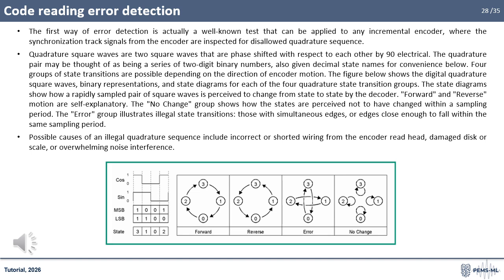The figure below shows the digital quadrature square waves, binary representations, and state diagrams for each of the 4 quadrature state transition groups. The state diagrams show how a rapidly sampled pair of square waves is perceived to change from state to state by the decoder. Forward and reverse motion are self-explanatory. The no change group shows how the states are perceived not to have changed within a sampling period. The error group illustrates illegal state transitions, those with simultaneous edges, or edges close enough to fall within the same sampling period. Possible causes of an illegal quadrature sequence include incorrect or shorted wiring from the encoder read head, damaged disk or scale, or overwhelming noise interference.